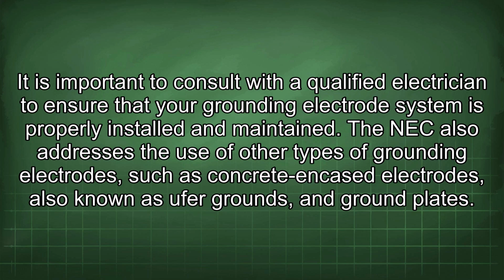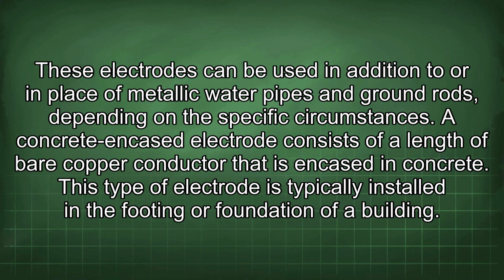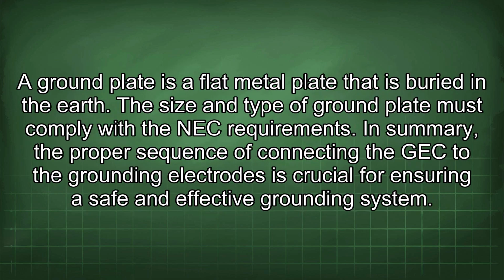The NEC also addresses the use of other types of grounding electrodes, such as concrete encased electrodes, also known as UFER grounds, and ground plates. These electrodes can be used in addition to or in place of metallic water pipes and ground rods, depending on the specific circumstances. A concrete encased electrode consists of a length of bare copper conductor that is encased in concrete. This type of electrode is typically installed in the footing or foundation of a building. A ground plate is a flat metal plate that is buried in the earth. The size and type of ground plate must comply with the NEC requirements.